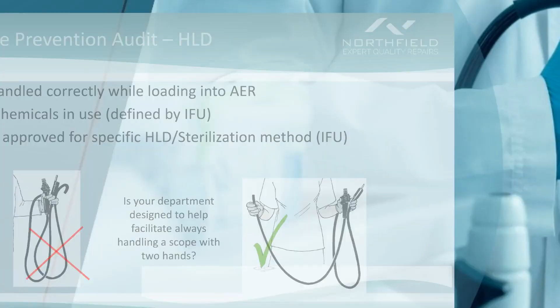Now, a quick word about sterilization, particularly for small diameter scopes like cystoscopes or your ureteroscopes. Always make sure that ETO cap is in place. I really wish they would call it something besides ETO cap, because you've got to use it even if you're not using ETO, if you're using hydrogen peroxide, for example, which I suspect most people are. But that cap still has to be in place.